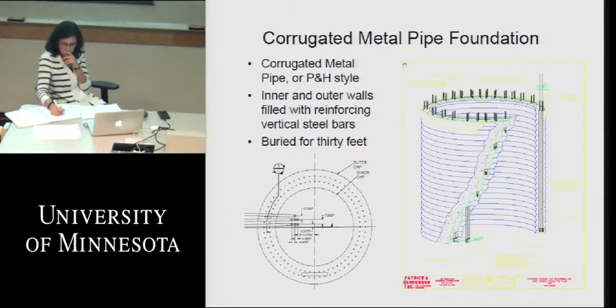It doesn't use a large footing, and so it needs to have better contact with the ground, deep into the ground as such, to make sure all those forces are accommodated. So it uses two tubes, essentially, this inner and outer wall, and then we put rebar in between the walls and pour concrete in between the walls, and this gives us a very solid foundation. And those rebar, we can tip with the threaded connections there, so we can make that flange mount to the tower itself. Okay, next slide.